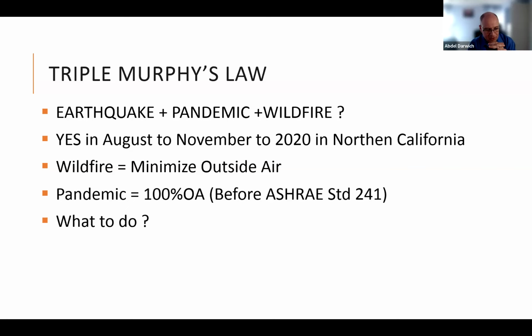Well, that was before. Some of you know there's a new standard, 241, on infection control in all buildings. This standard tells you that you don't actually need to go to 100% outside air in a pandemic — there are calculations that give you a certain airflow, but it's not 100%, which is good. So now if people ask what to do during a pandemic and wildfire, go to the 241 airflow and filter as much as you can.